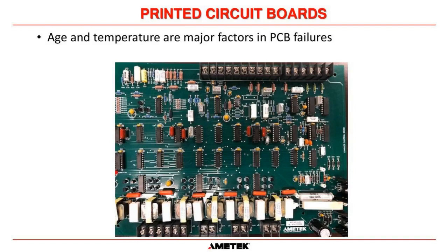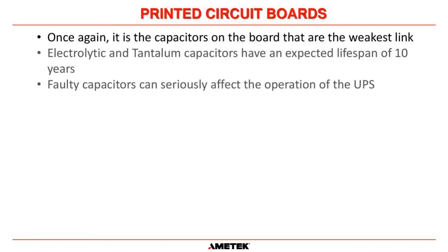Printed circuit boards can fail. There's absolutely no doubt about it. And once again, it goes back to the capacitors. This is a rectifier control board for one of our UPSs. You can see on the bottom right here there is a DC electrolytic capacitor. And what a lot of people don't realize is these little yellow capacitors here are tantalum capacitors, and there's another one there as well. Tantalum are basically an electrolytic capacitor as well. All those capacitors are affected by age and temperature, so they still have to be replaced as per the manufacturer's guidelines. And the guidelines for printed circuit boards are 10 years because of those electrolytic and tantalum capacitors.